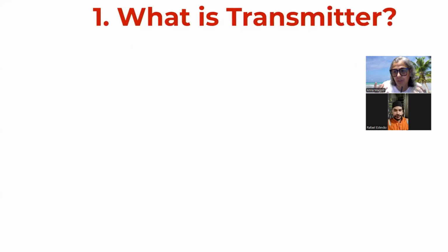Do you have some special tools to test the transmitters? Yes. I have specific tools and specific equipment. For example, I need standard instruments, like a standard pressure transmitter. Today, for example, my pressure transmitter is not good. It's very incorrect in the field. Then I will take my standard instrument from my workshop and go to the location where the instrument is installed, and compare the value.